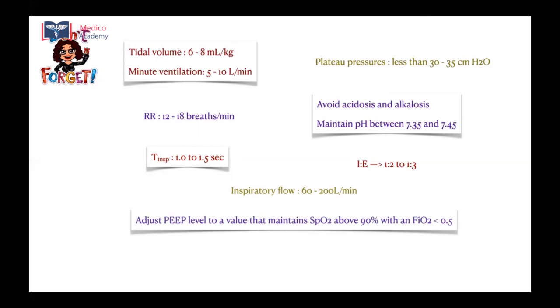Adjust the PEEP level to a value that maintains an SpO2 above 90% with an FiO2 less than 0.5 or 50%, because an FiO2 of less than 50% can be safely delivered to patients without significant oxygen toxicity or significant side effects. And the trigger, last would be the trigger: a flow trigger of 3 to 5 liters per minute or a pressure trigger of -3 to -5 centimeters of water will be adequate in adult patients. So that is about how to set a ventilator.